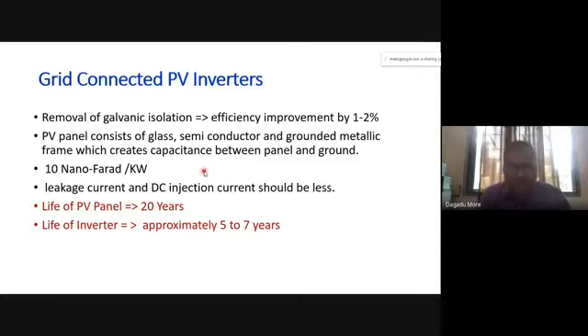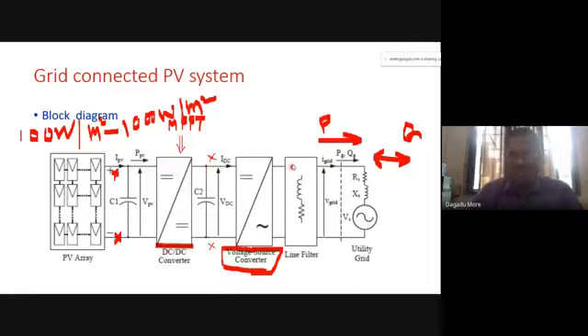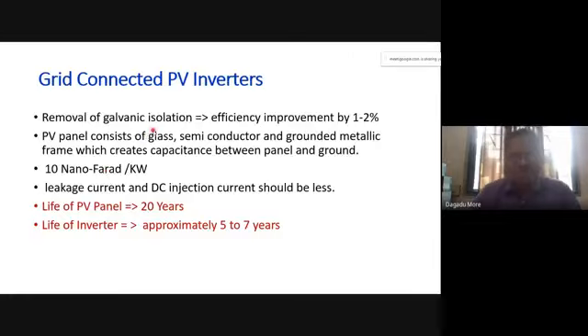Whereas here, we have not shown the isolation. Sometimes the grid and PV system are isolated with a transformer, and that we can call galvanic isolation. But if you use a transformer in between the PV system and grid just for isolation purposes, then definitely overall efficiency will be decreased by 1 to 2%.